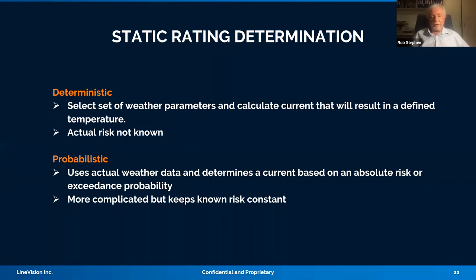They do not change. Operators and designers know that on a certain conductor at a certain voltage, you will get this certain rating. So there you look at two different kinds. The first one is deterministic, which is used largely around the world, where you select a set of weather parameters and calculate the current that will result in a defined temperature. That temperature is normally defined as a design temperature, or the temperature at which the conductor will be at the height above ground as defined by law.